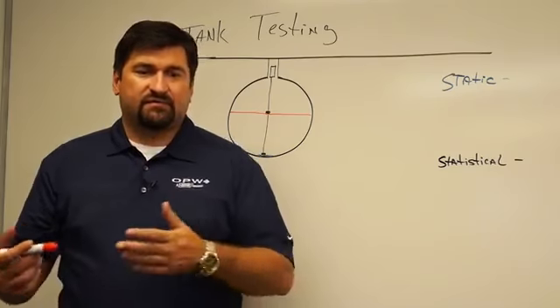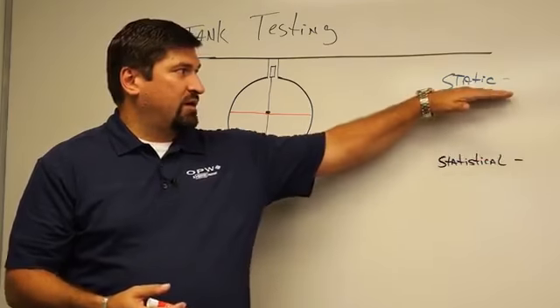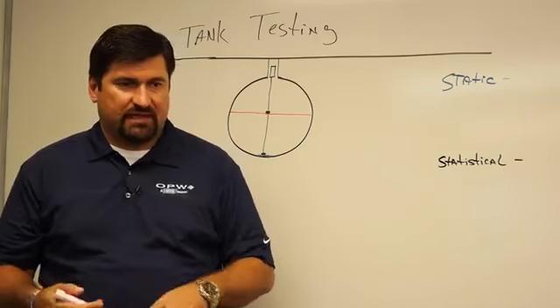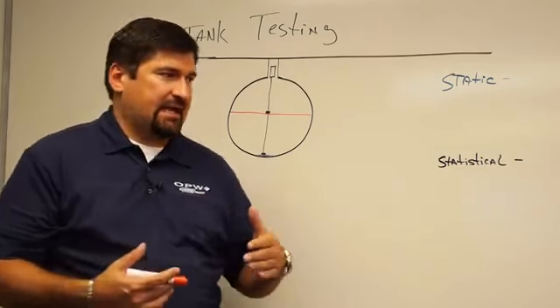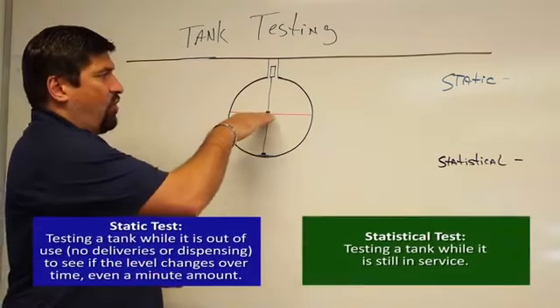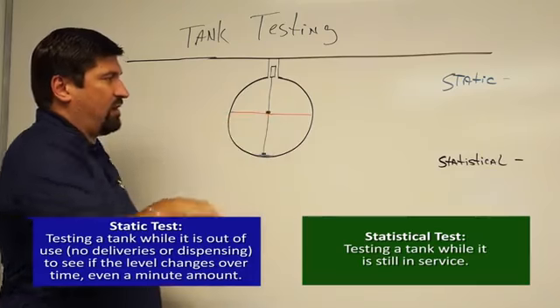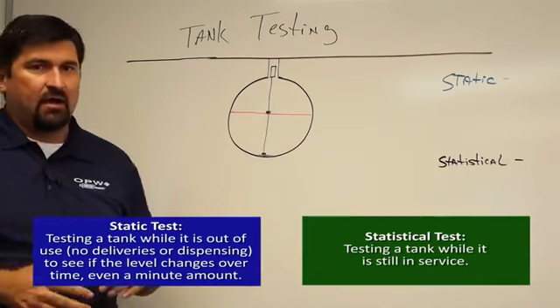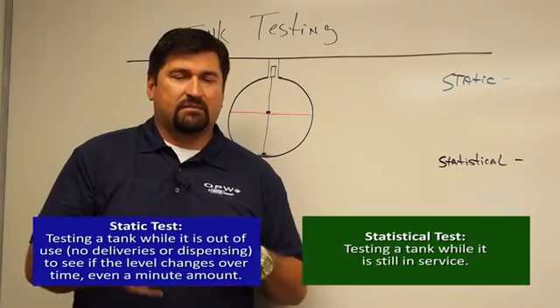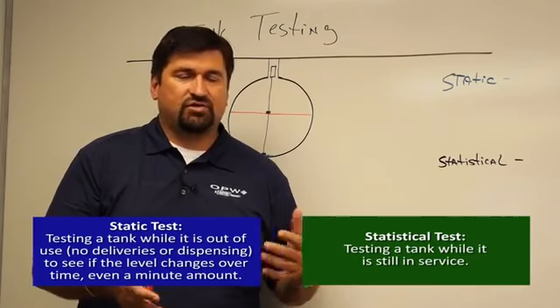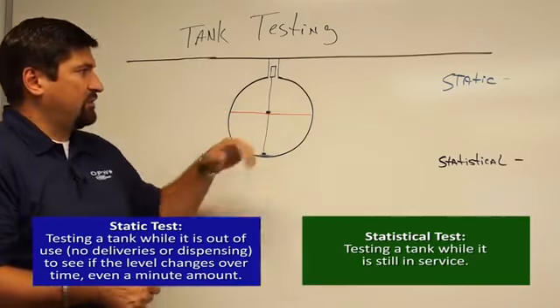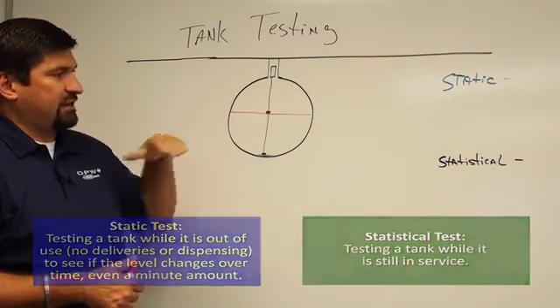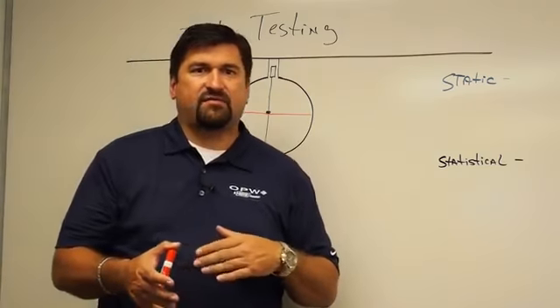Well, there's two types of tank tests that you can do. One is a static test, one is a statistical test. When we start looking at a static test, it is a moment in time. I'm looking for a specific level in the tank over a period of time. And the minimum at most tank testers is about 2 hours. So basically what I'm looking for is a snapshot for 2 hours to make sure that that tank's volume never changes.